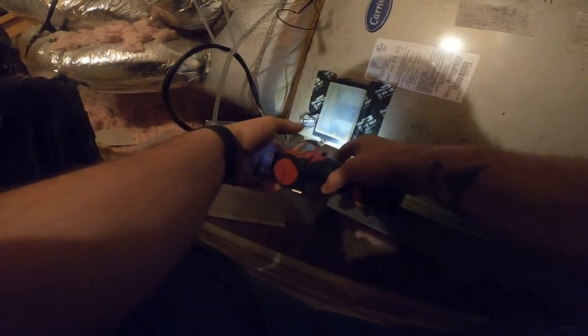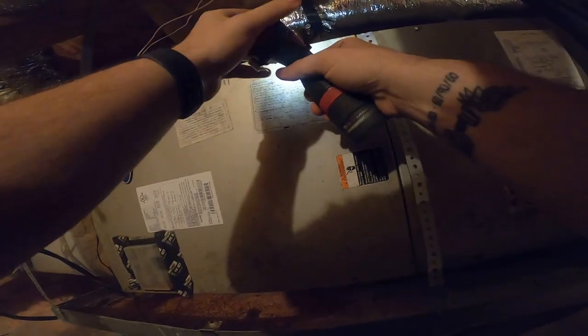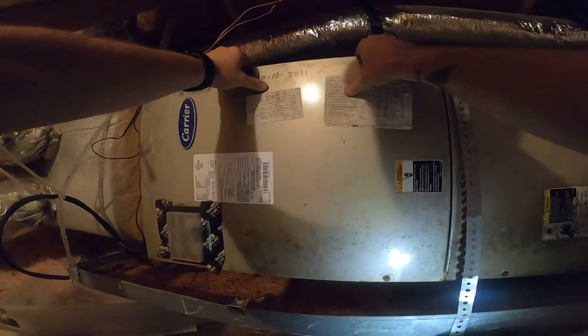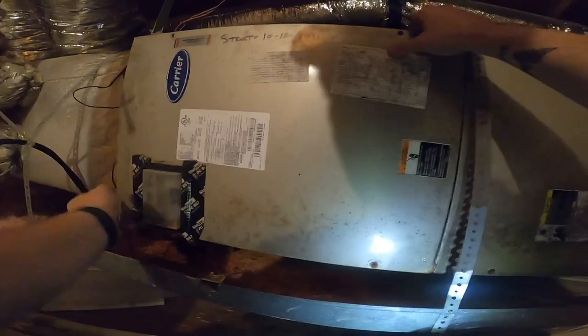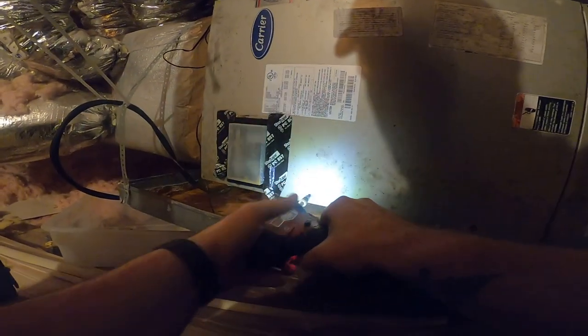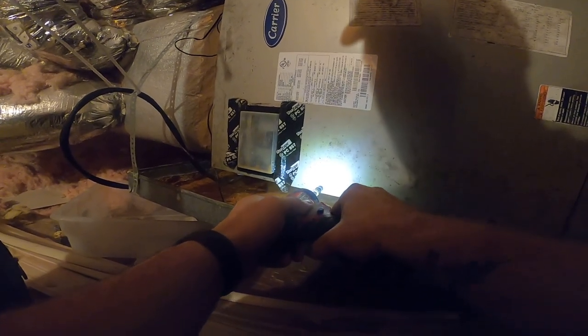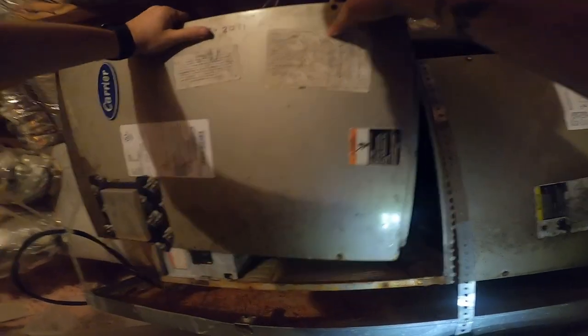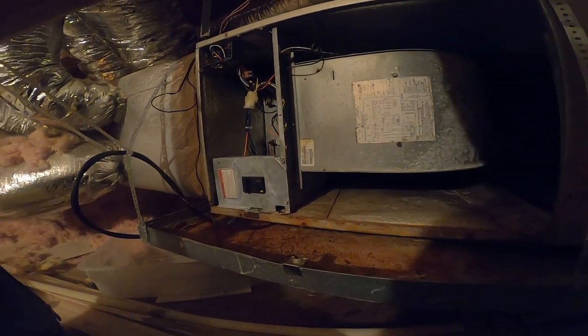We have a Carrier air handler here, 2011. No indoor blower motor screw missing there. The condenser was running so the system has been freezing. They put the screw here. We have another hung unit here, hanging with some strapping. Good old X13 fan motor — I can hear that module making noise.